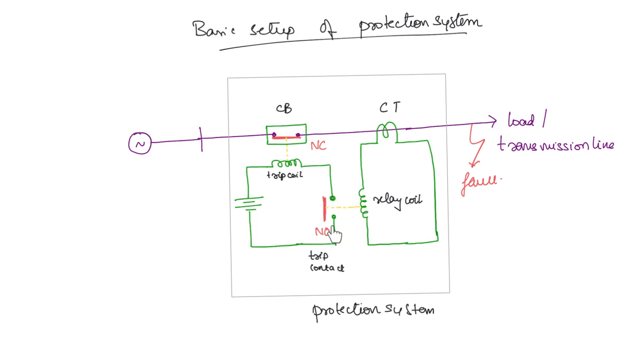Once this contact is closed, a current will flow because of the battery here. So now the current will flow in the trip coil. Under normal working conditions, this contact is closed. Now once the trip coil is energized during a fault, this normally closed contact is attracted towards the trip coil and becomes open circuited. This contact will no more be closed. If you consider the main circuit, the current was flowing from here, but now this contact is open because of the fault, so no current will flow towards the fault. So this is the basic setup that we have discussed.